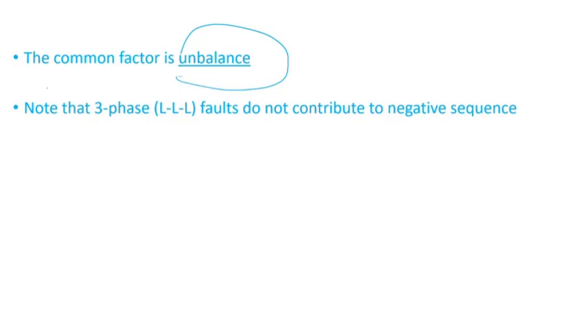So three phase or line to line to line. So all three phases. So if you take all three phases, basically phase A, B, C, if somehow they became shorted altogether, and they can be to ground or without ground involved, it doesn't matter. Typically, they do not contribute to negative sequence.